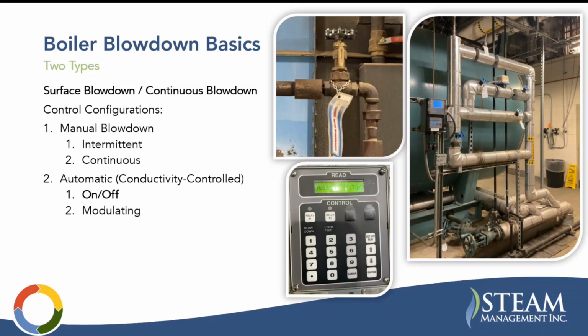The control configurations here, you can have different controls. More crude controls are going to give you more blowdown flow. So just upgrading those controls can represent an energy conservation measure as well. But it also may represent a large amount of blowdown flow that you can capture. There's manual controls like intermittent or continuous. Continuous would be something like this with a valve with a position indicator on it that's adjusted from time to time by the boiler operators to try to ride a certain TDS level in the boiler. And then intermittent would be a valve that they come out and actually just blow it down, similar to the way they do bottom blowdown.